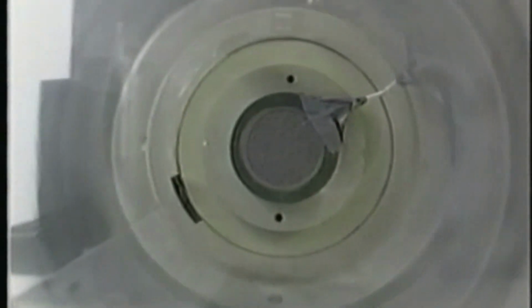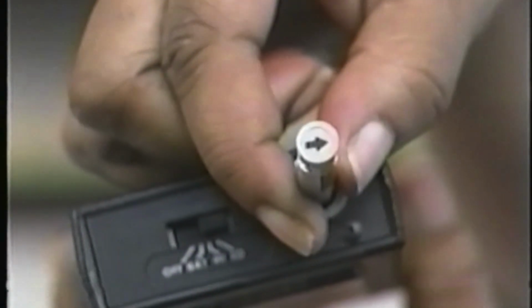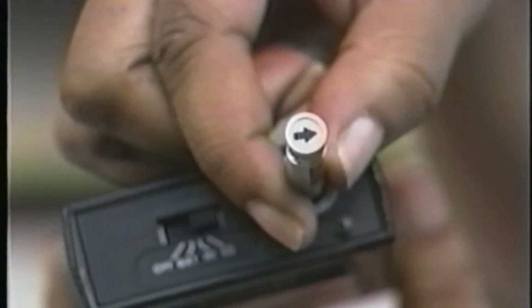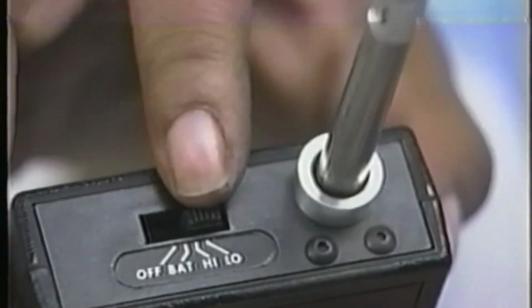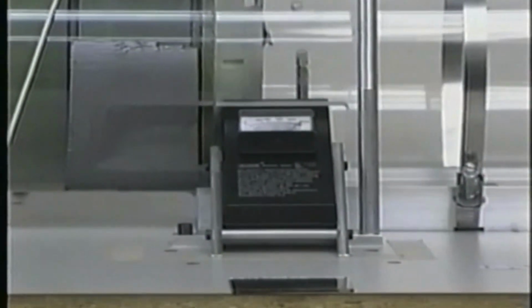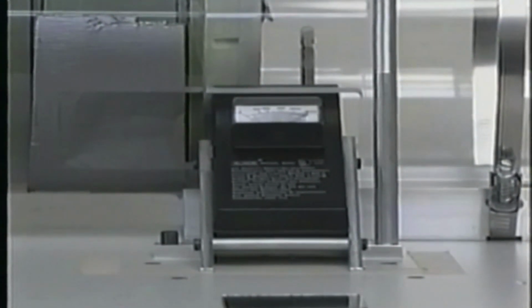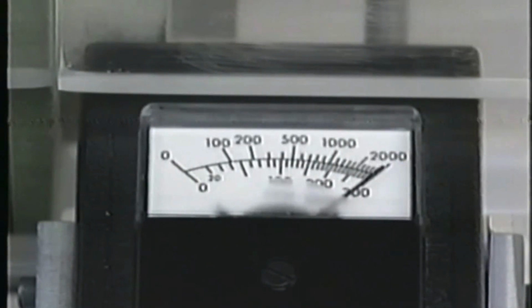To make the high span adjustment, set the instrument in the wind tunnel with the probe positioned so that the airflow is in the direction of the arrow on the probe. Set the instrument to the high position. Then set the wind tunnel to 2,000 feet per minute and turn the high span adjustment screw, labeled H span on the left-hand side of the instrument, until the meter needle lines up with the 2,000 feet per minute division.